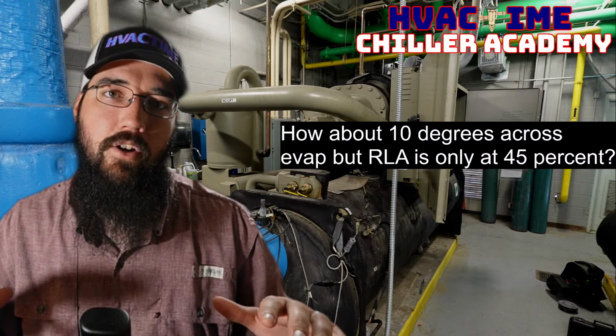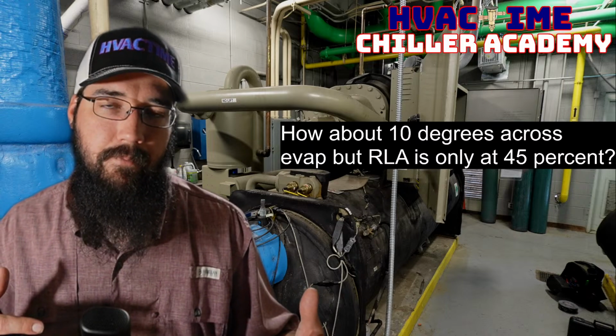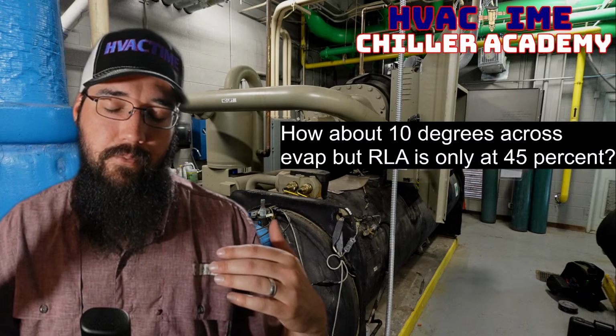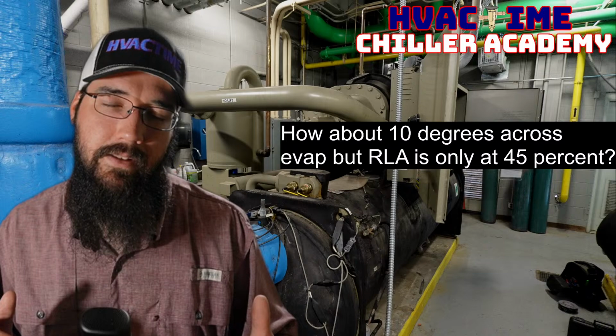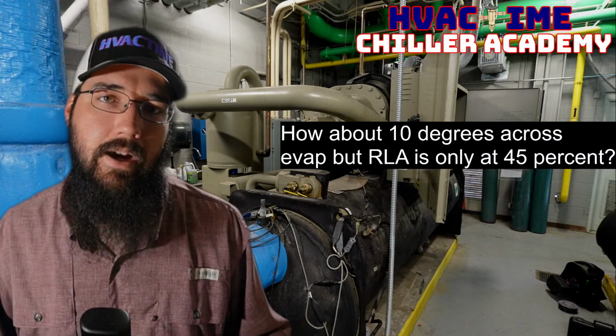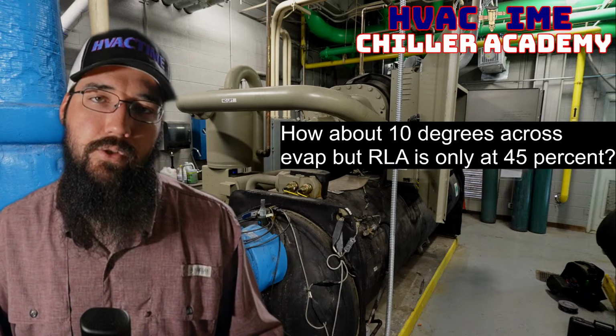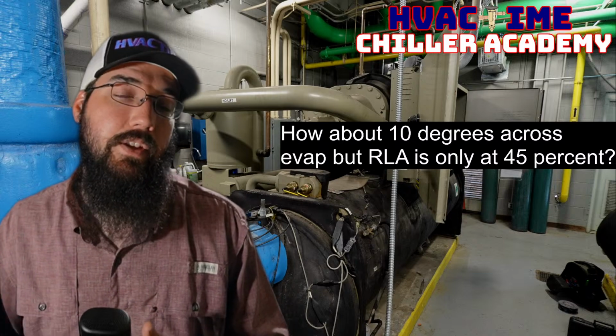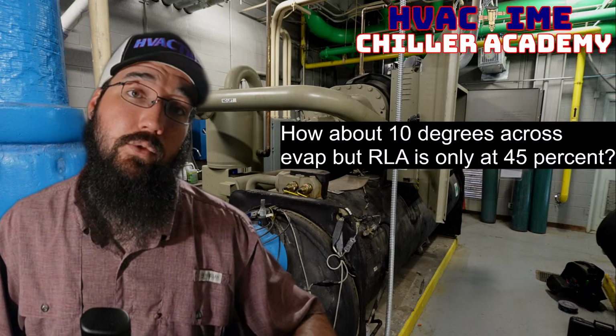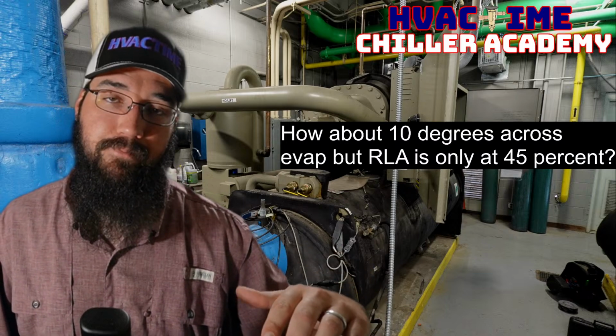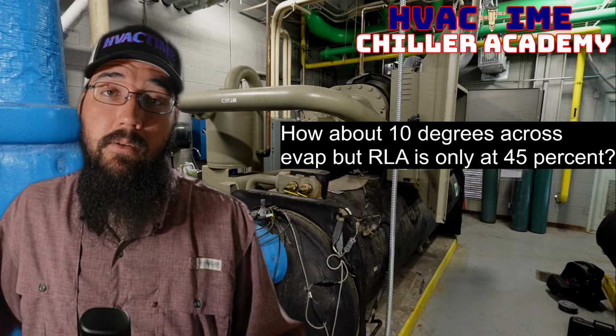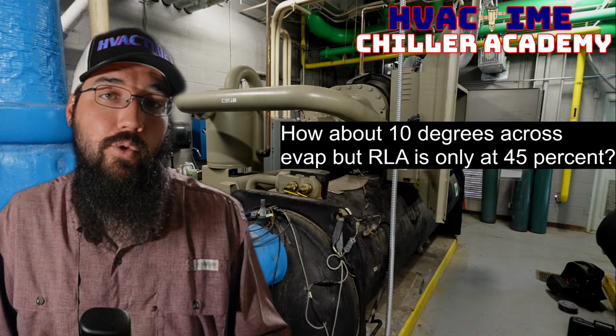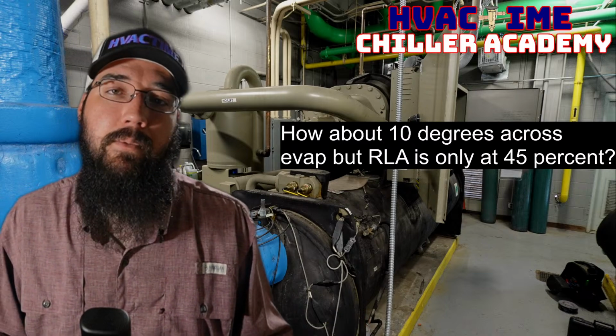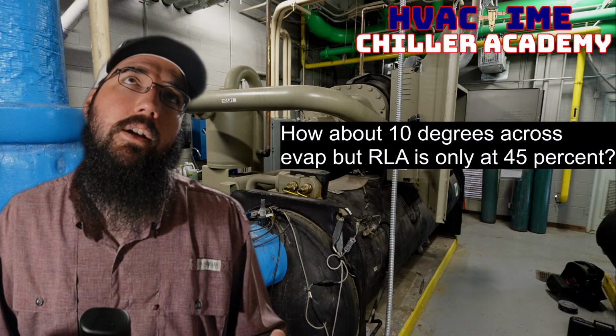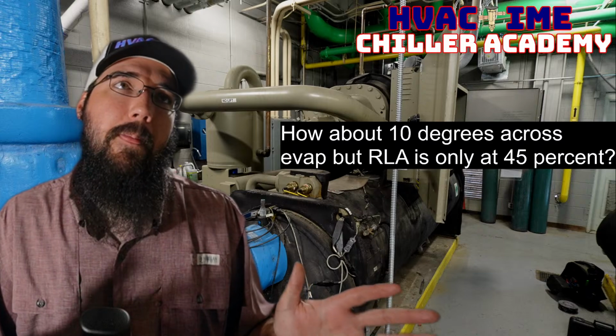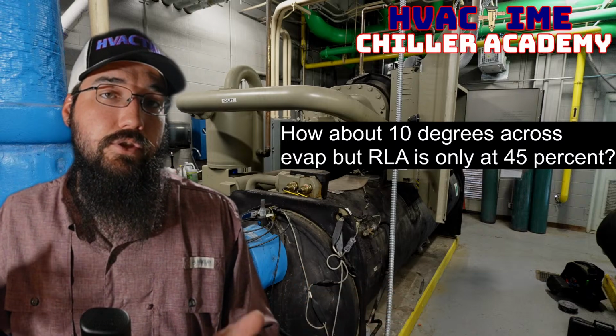The lower we can maintain our lift across the compressor, and this is true for any compressor, this isn't just a centrifugal thing, the less compression we have to do. And the less compression we have to do means the less work we have to do to still move the same volume of BTUs. So what that could look like is, one, you may be running a higher chill water set point. So instead of 40, 42, 45 degrees, maybe you're running 48 or 50 degrees, depending on your application, or if you've got a temperature reset happening. Depending on your circumstances, you may have a higher chill water set point.